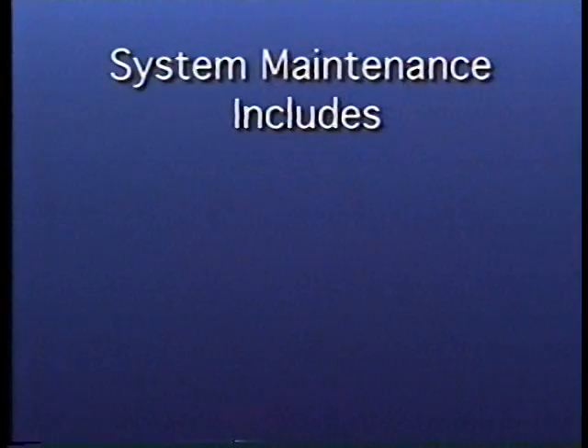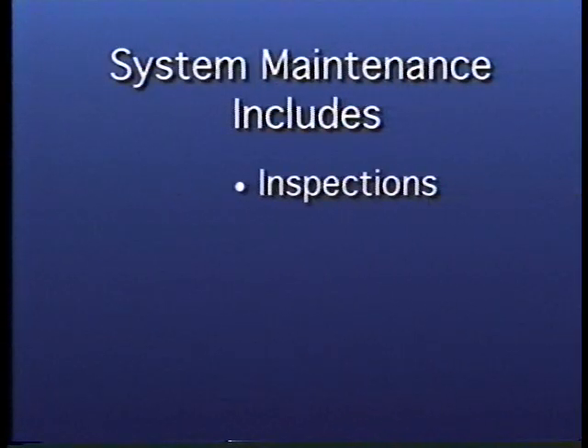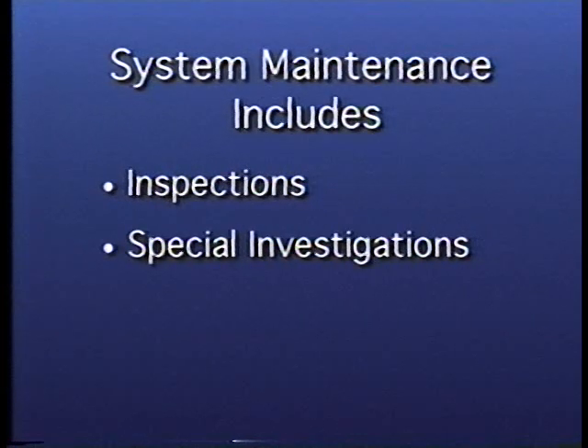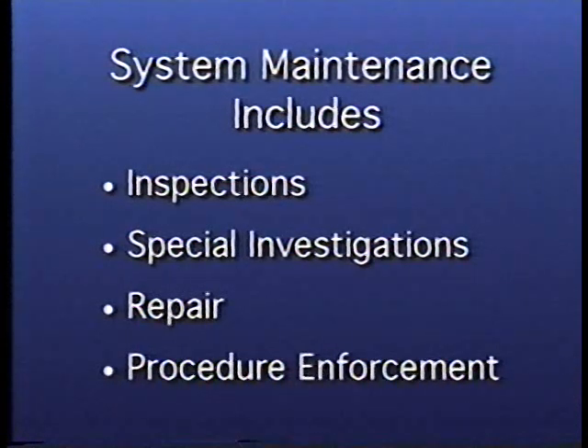The Fire Protection Handbook defines inspection as an organized methodical procedure for determining the operating condition of devices and equipment. The handbook also provides information on the qualifications of personnel who will be responsible for fire sprinkler system maintenance and repair. Maintenance of protection involves making the inspections as well as performing any special investigations or tests bearing on the performance of the devices and equipment. Maintenance also includes taking action to repair or keep devices and equipment in dependable operating condition, as well as ensuring the proper procedures are followed by personnel responsible for the performance or use of the equipment.